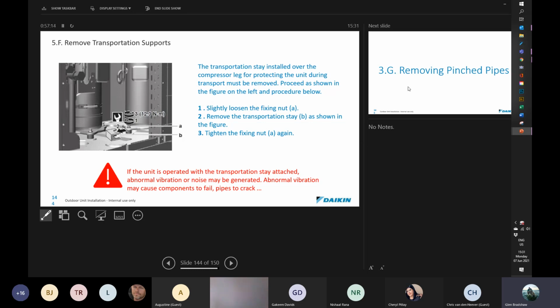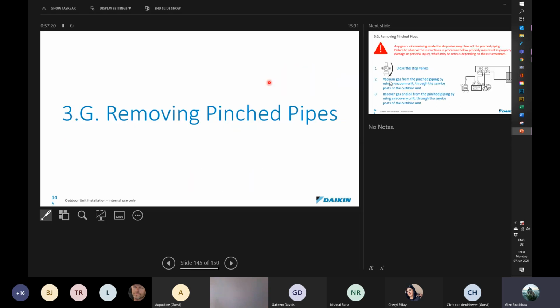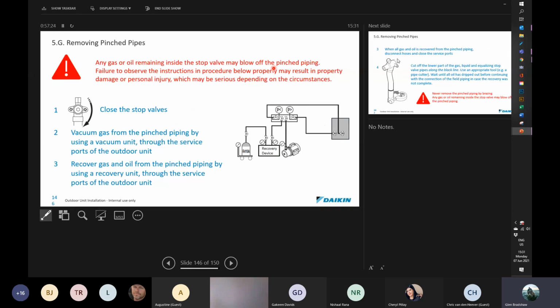All right, then once that's done, you are basically ready to start your piping, which we will talk about next week. Then removing the pinched ends. Okay, believe it or not, we've had systems where we've gone to commission and found that the piping is blocked, only to find that when the guys welded the piping onto the unit they hadn't removed the pinched end. They just sleeved the piping over and welded it up.